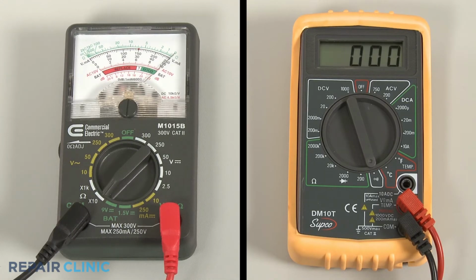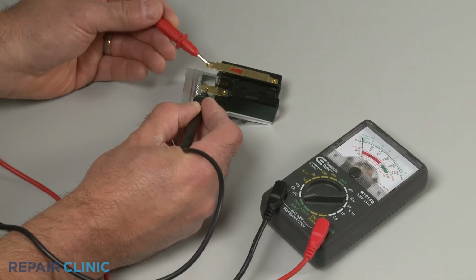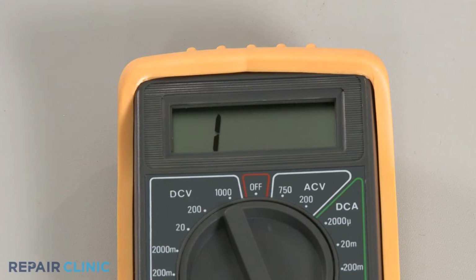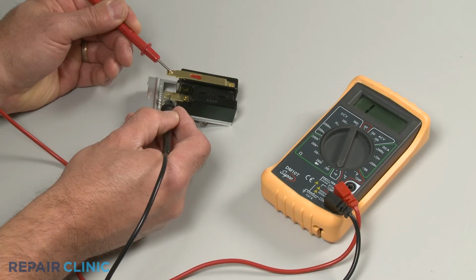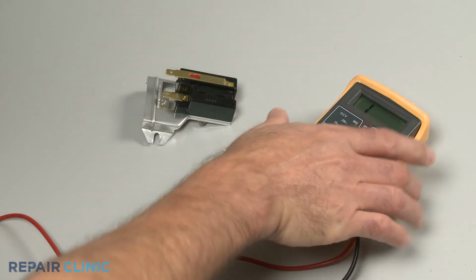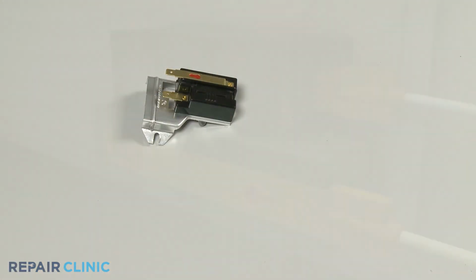If the meter reading shows 0 ohms of resistance, the sensor has continuity and is not the cause of the igniter failing to glow. However, if the meter's needle does not move, or the digital display does not change significantly, there is no continuity, which means the sensor has failed and will need to be replaced.